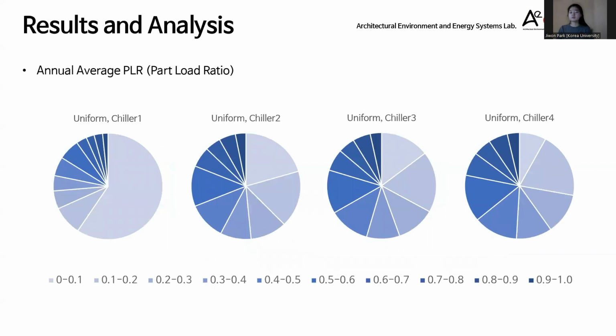The annual part load ratio for each of the four chillers when operating with the uniform algorithm is shown in the radial graph. The darker the color, the higher the PLR, indicating higher operating load. In the uniform algorithm, it is observed that all four chillers operate at a PLR of 0.2 or lower for over 20% of the operating time.